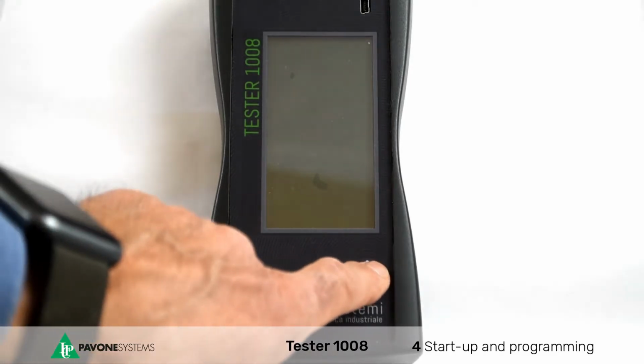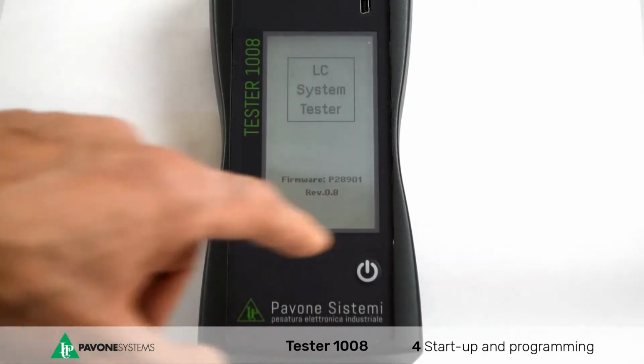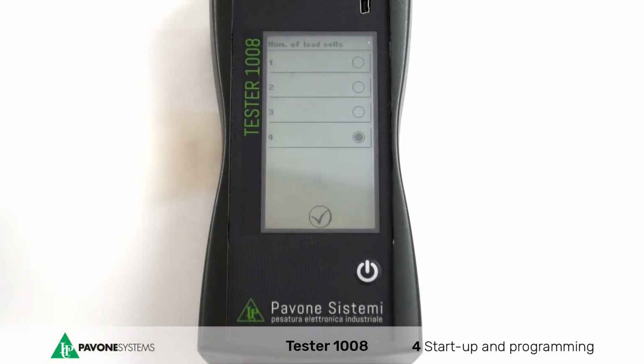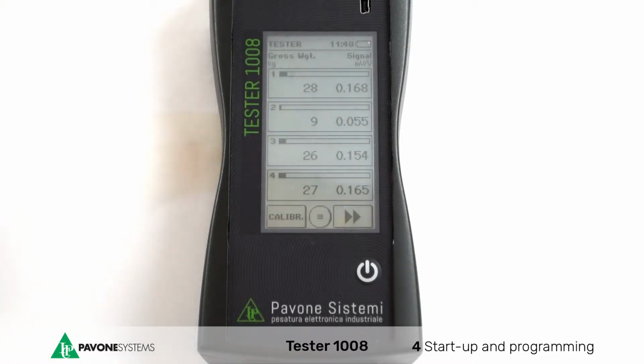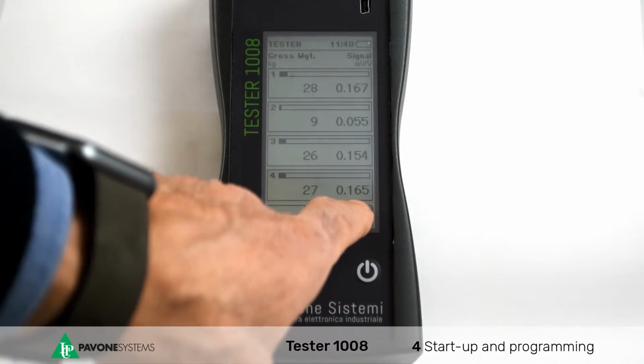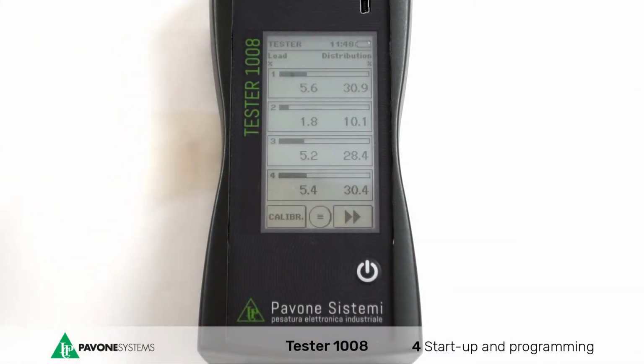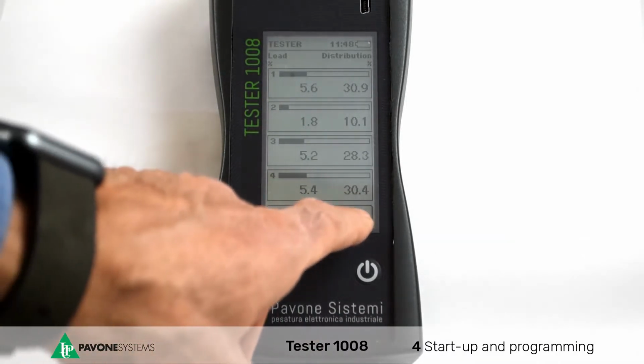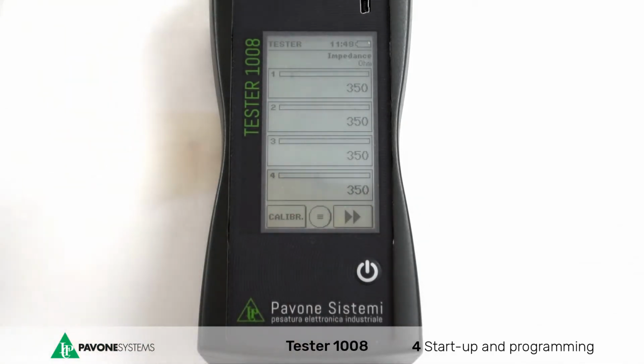Let's begin with the startup and the programming of Tester 1008. The first setting that has to be selected is the number of the load cells connected to the junction box. Later, the Tester 1008 will start with the reading of the impedance values. You can change the screen with the right arrow key and access the load distribution in percentage and the detected impedance values. It is possible to read some data even without programming.